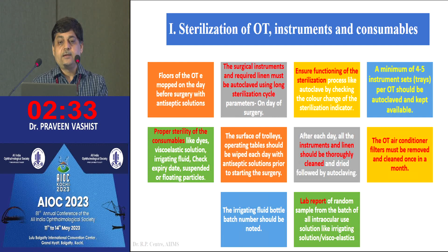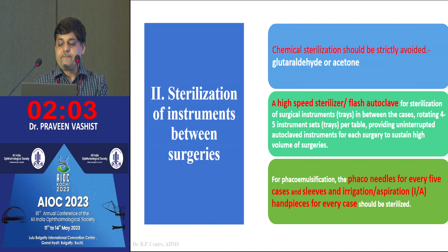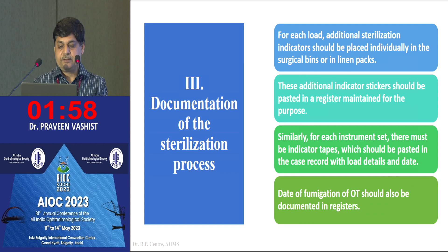I think there's no need to go into detail of each and everything. In fact, for instruments, they said chemical sterilization should be strictly avoided, such as glutaraldehyde and acetone. You should use high speed sterilization or flash autoclave for sterilization of surgical instruments in between the cases. And for phacoemulsification, the phaco needles for every 5 cases, and sleeves and irrigation aspiration handpieces for every case should be sterilized. Documentation, Dr. Harpreet has mentioned, in fact, they have given guidelines related to documentation of the sterilization process.